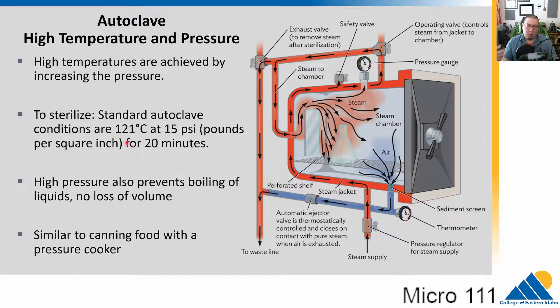If you heat to 121 degrees C for around 20 minutes, this will completely sterilize whatever is in there. You can also do this with instruments and metal things. But autoclaves, because they use high heat, can't handle certain plastics — only some plastics are autoclave safe. People have accidentally put the wrong plastic in the autoclave and it melts and gets all over the place.